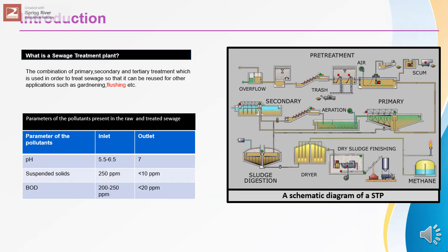Sewage mainly constitutes of suspended solids and BOD. The pH is slightly acidic, in the range of 5.5 to 6.5. The suspended solids are at a concentration of 250 ppm at the inlet, and the expected concentration at the outlet should be less than 10 ppm. BOD — biological oxygen demand — is the amount of oxygen required by micro-organisms to destroy biodegradable organics. This is around 200 to 250 ppm at the inlet, and at the outlet it should be less than 20 ppm.